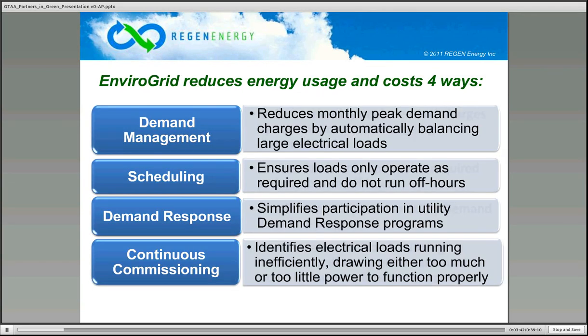The EnviroGrid controller reduces energy usage and costs in four ways. The first thing is demand management. This is load balancing. Basically, what we're doing is making sure that not all of your loads come on simultaneously, as can happen on a hot summer day. And so by balancing that load, we reduce the peak for the month and thereby the charges for that month.